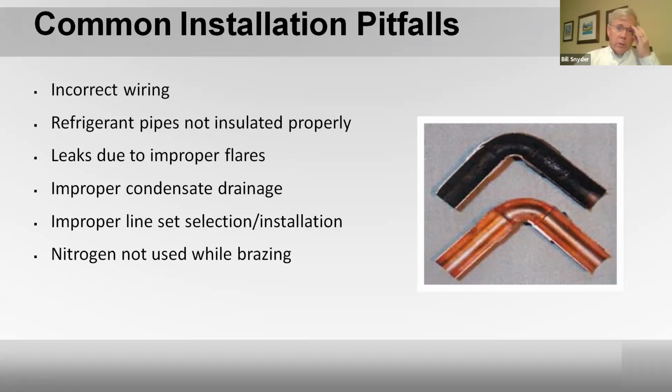100 mesh screens, or it'll find the cap tubes. There's some cap tubes in the system, and there's also the LEV, linear expansion valve. There's all places for that black stuff to go. It'll find a place, plug up. Now you've got a real problem trying to find it. Where those 100 mesh strainers are, they're a strainer that is pressure fit inside the pipe, so you can't see any dimple, can't see any place that it actually is.